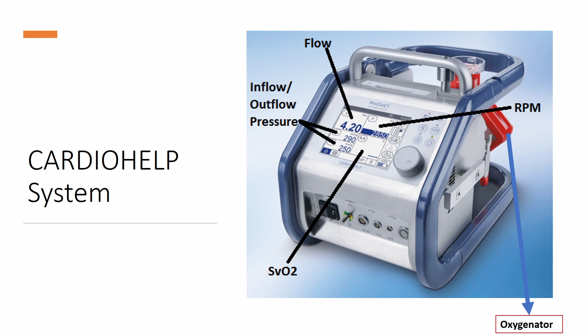And at the very back is the oxygenator. And the oxygenator is kind of the lifeblood of the machine. We always want to watch this throughout the person's time on ECMO, because sometimes you can see little white clots in it, and those are fibrin strands that are a harbinger of the entire machine clotting off. And as you can think, once that machine clots off, it's kind of game over for the patient.